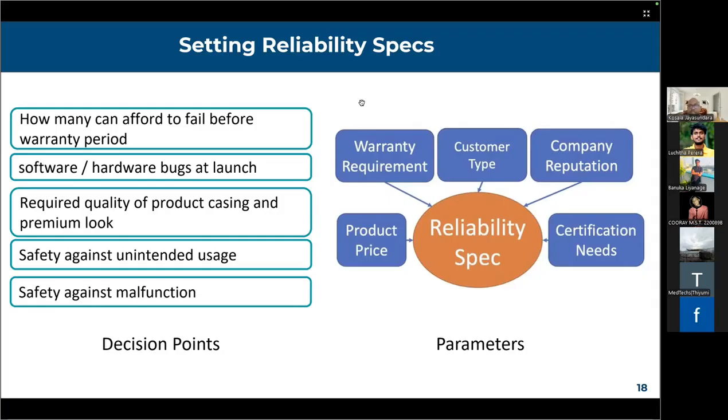And sometimes products are quite complex. CT scanners, MRI scanners, they are really complex. You have thousands of individual components, and you have to make sure that bugs and failures are contained. You can't have zero bugs ever in a medical product development. When you are launching the first version, you can have a number of bugs, which should not have any safety issue for the patients beyond those green, yellow levels, or for the accuracy requirements. But you can have bugs. You have to properly mention those bugs that are remaining when you are launching version 1.